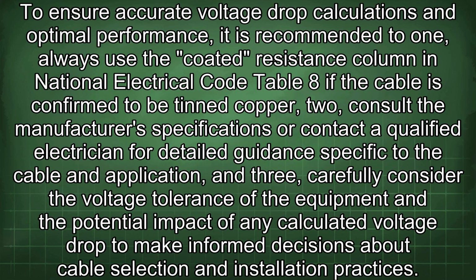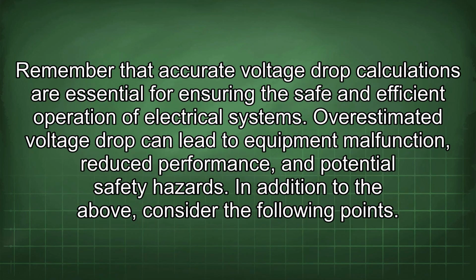To ensure accurate voltage drop calculations and optimal performance, it is recommended to: 1. Always use the coated resistance column in National Electrical Code Table 8 if the cable is confirmed to be tinned copper. 2. Consult the manufacturer's specifications or contact a qualified electrician for detailed guidance specific to the cable and application. And 3. Carefully consider the voltage tolerance of the equipment and the potential impact of any calculated voltage drop to make informed decisions about cable selection and installation practices. Remember that accurate voltage drop calculations are essential for ensuring the safe and efficient operation of electrical systems. Overestimated voltage drop can lead to equipment malfunction, reduced performance, and potential safety hazards.